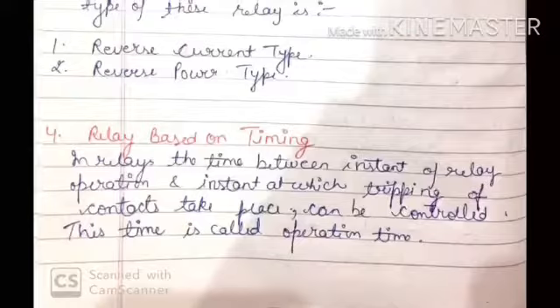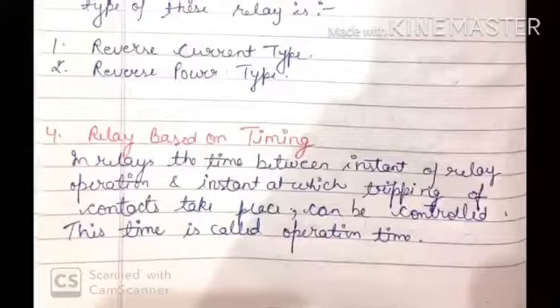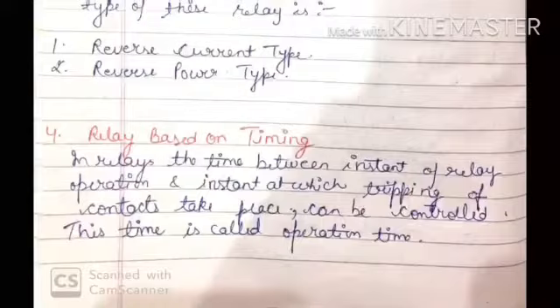Timing-based relays are of three types. First, instantaneous type: no time is lost between the operation of the relay and the tripping of contacts — no intentional time delay is provided. Second, definite time lag type: in this type, an intentional definite time lag is provided between the operation of the relay and the tripping of the contact. Third, inverse time type: in this type, the operating time is approximately inversely proportional to the magnitude of the actuating quantity.